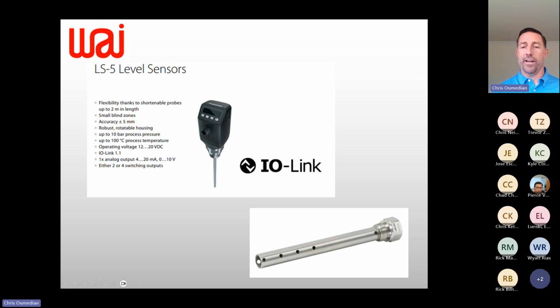We also have this device, a coaxial tube that goes around the probe, used for specific media. I'm actually working an application now in a hydraulic tank that's constantly being cleaned, so the tank has waves of fluid — 6, 8, 12, even 16 inches — that would make a non-contact sensor freak out. Having this tube around it tempers or mitigates the fluctuation as waves hit the metal tube, while the fluid still rises and lowers through small ports or holes in the side.